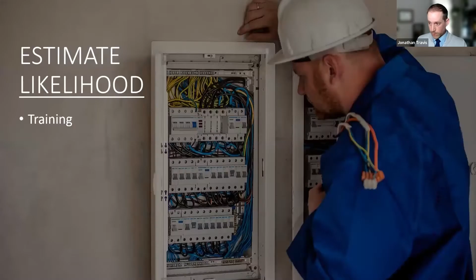So that's not good. Whenever I look at estimating the severity of a certain job, I say, okay, what's the voltage? Well, it's above 30 volts. All right, that means we can get a shock hazard that could kill me. And can there be an arc flash? If the equipment is above 240 volts, and again, we don't want to get too scientific here, but for the most part, if it's above 240 volts, the answer is yes, there could be an arc flash there. And that's really all you got to know. So we just simplified those two steps for pretty much 99% of the work the electrician is doing: there's going to be a shock, there's going to be an arc flash, and then they can go to the next one.